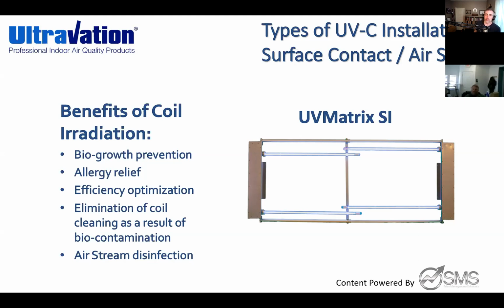But for larger commercial solutions, we want to make sure everything is racked properly. The spacing is set up for the right disinfection rate over the coil surface, especially with tall coils where you may need 2 or 3 racks high. The biggest thing is, back in the day, we used to mount bulbs 24 inches apart vertically. As goals for higher disinfection rates increased, they found that bulbs should be mounted about 12 or 14 inches apart vertically.